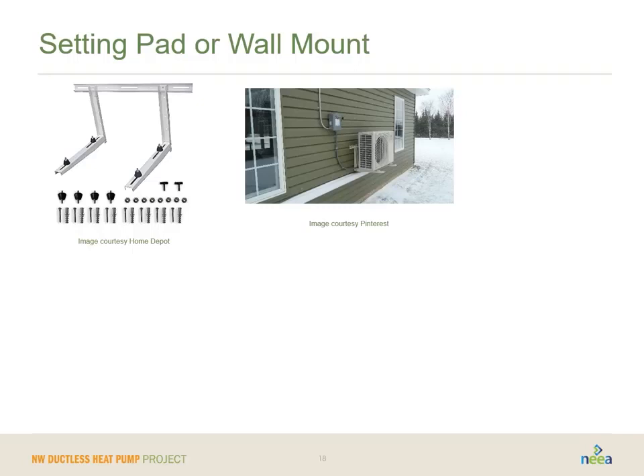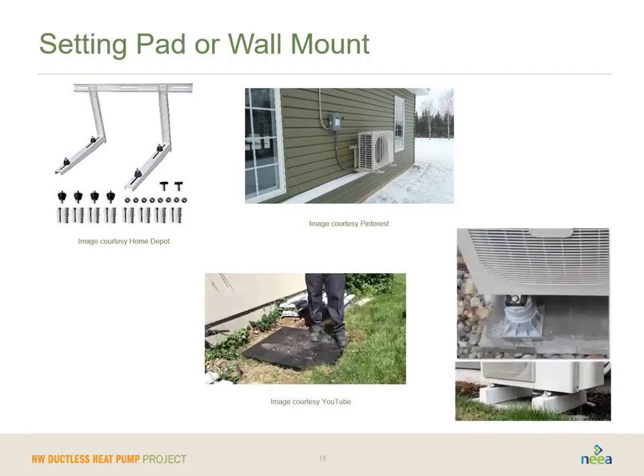compressor on the outside. If you're installing one on the ground, you're going to need to have one of these pads, and it can be a concrete pad, or they sell specific plastic pads just for this purpose. And we'll talk a little bit more about setting this, but you'll want a pad, you'll want some risers. You see a couple different versions of those in the lower right-hand corner, and those are enough to give you some clearance off the ground. So whether it's leaves or debris, running water, or even a little bit of snow, you've got that clearance underneath your compressor.